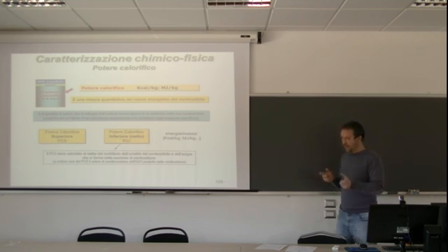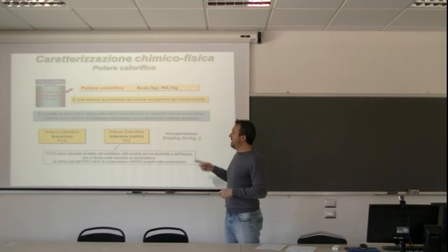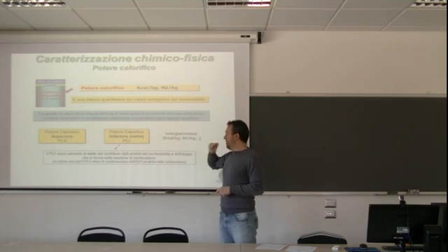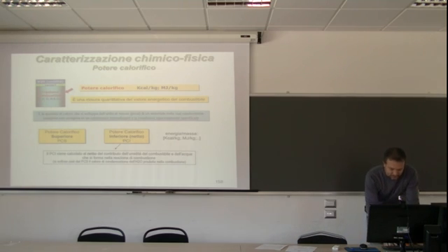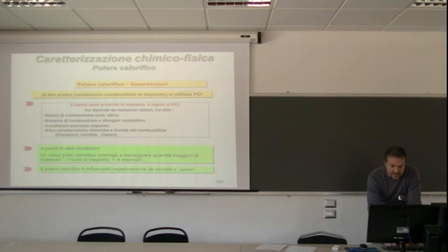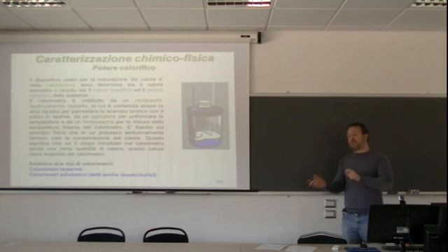And so this difference can be considered, distinguishing low and high heating value. The machine measures the heating value. Then you can move from low to high heating value using some very simple formula.